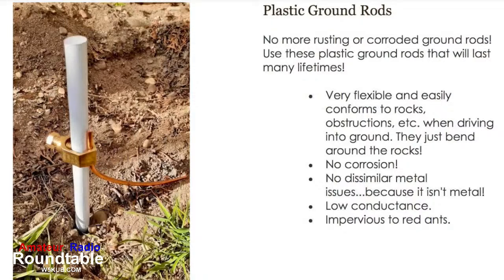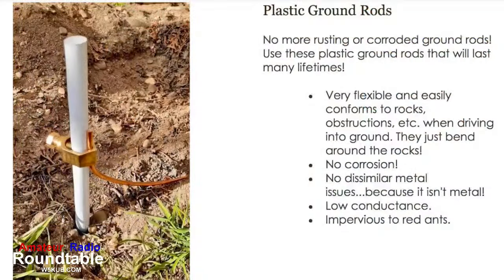The UFER ground is a number 4 rebar or larger bent in the shape of an L, and it's tied to the rebar before they pour the footing. It sticks up, I forget how many inches, 6, 8, 10 inches, and then it goes up the wall to a box that's in the wall usually, and that's where your intersystem bond is. That's where everything is tied into that box. So for some folks, it's going to be hidden in that box, and the only way you could access it is with clips, because you can't get access to some of these things. Many houses will have one UFER ground.